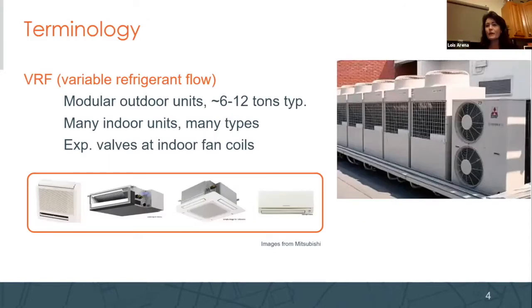So variable refrigerant flow is what VRF stands for. They're generally modular outdoor units, approximately 6 to 12 ton size. That's the scale we're talking about. One outdoor unit can be attached to many indoor units of many types. And you have the expansion valve, which does the extraction or input of the heat into the space in the indoor unit, the terminal unit, what we call.